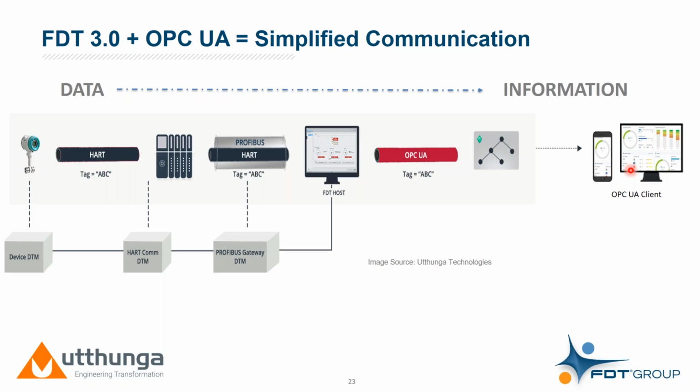The advantage of using OPC UA is that it passes not just the data value, but also the metadata associated with it. For example, a process value transmitted from this field device to the OPC UA client is transferred as an analog item type by the OPC UA node.